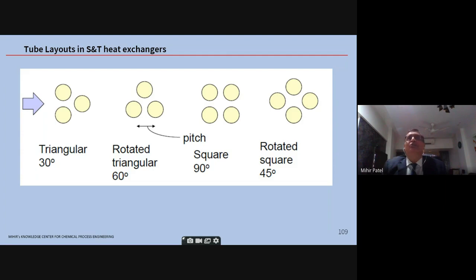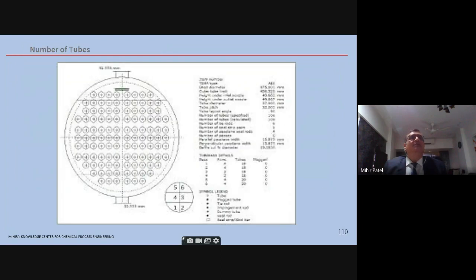So you can have a 1 inch tube on 1.25 inch pitch, or a 19 mm tube on a 25 mm pitch. Then the next slide. So the number of tubes. So this is a typical tube layout as given by HTRI, for example. Okay. So there is a 6-pass exchanger on the tube side. 1, 2, 3, 4, 5, 6 at the bottom. You can see these are the typical tube layouts.